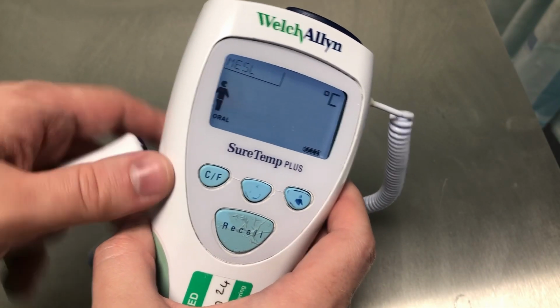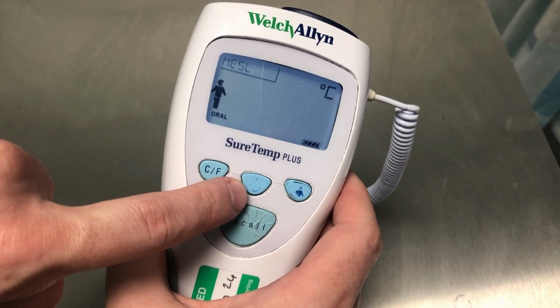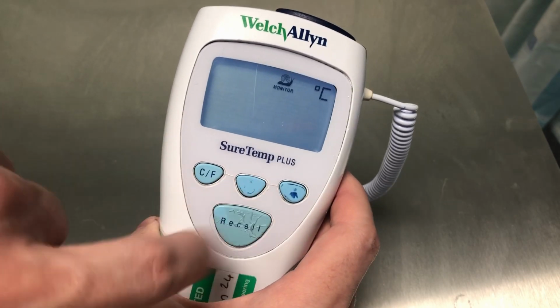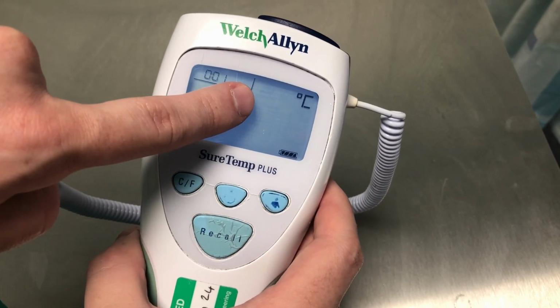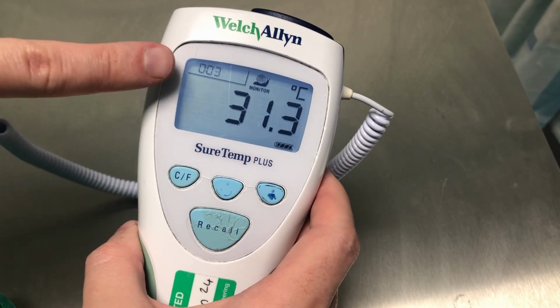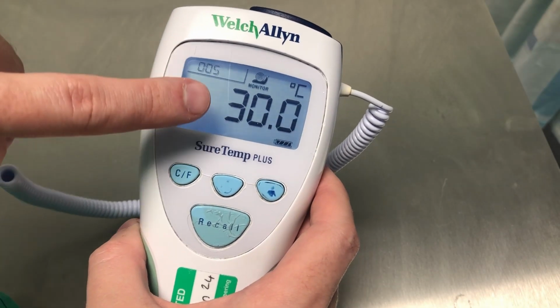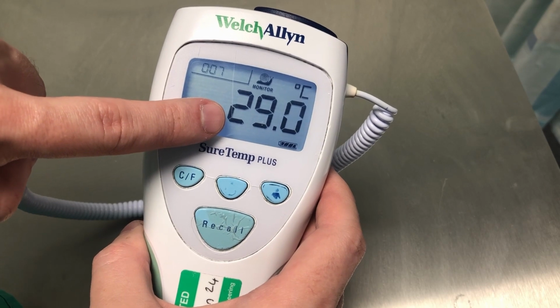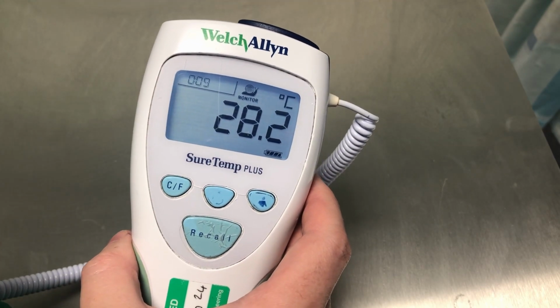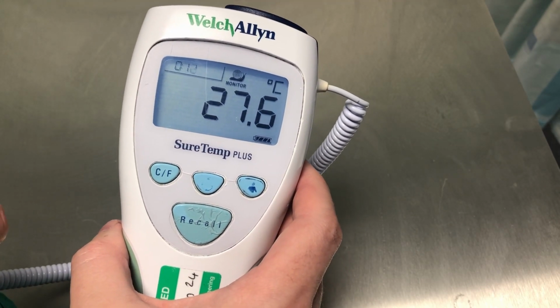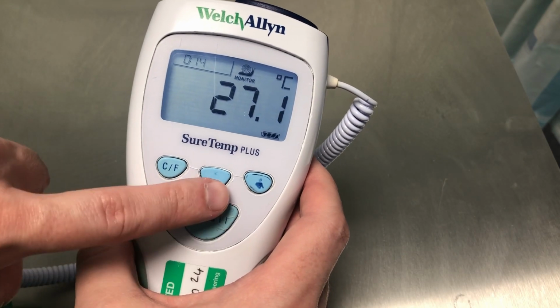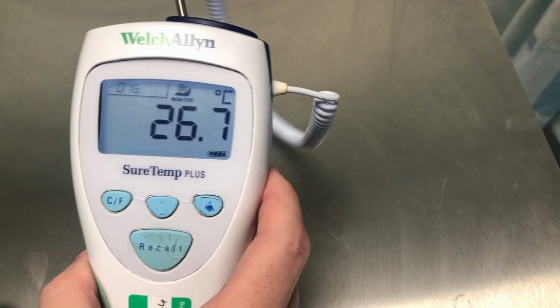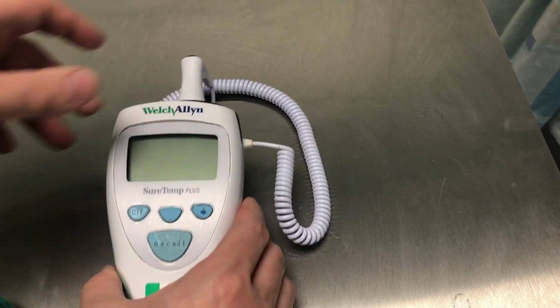So if you cannot get a temperature or you force enable it, continuous monitor mode operation is normally used when difficult situations prevent taking accurate temperatures in normal mode. Maintain contact with the probe and tissue for at least 3 minutes for accurate oral temperature and 5 minutes for accurate axillary temperature measurements. Monitor mode temperatures may not match identically to predicted normal mode temperatures because of the ambient temperature influence and other factors.